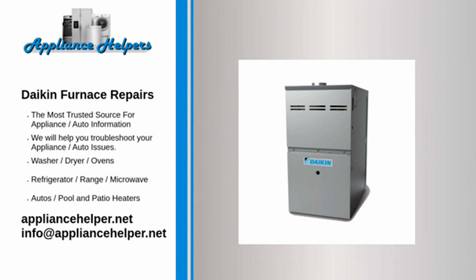The furnace runs but can't keep the house warm. If your furnace is properly sized for your home, then it should keep your home warm even in extreme cold. If it runs constantly but isn't providing enough heat, the likely causes are: a dirty filter that must be washed, only if the washable type, or replaced; the filter is the wrong type for your furnace and restricts airflow, so should be replaced; the filter is installed backward, an issue that can be checked by looking for the arrows on the filter frame that show proper installation direction with the flow of air.